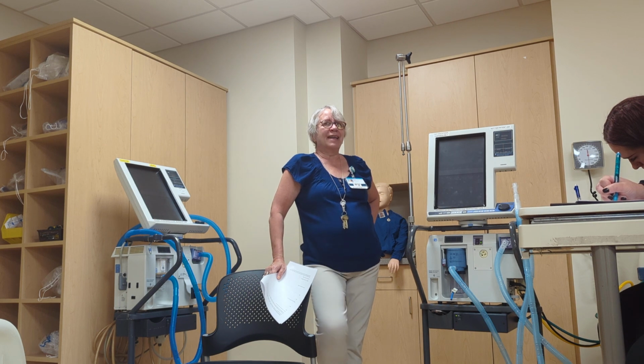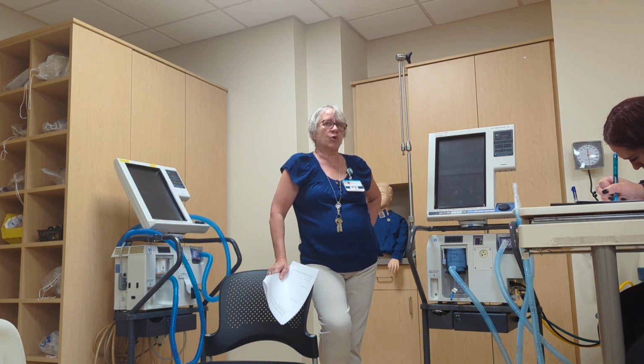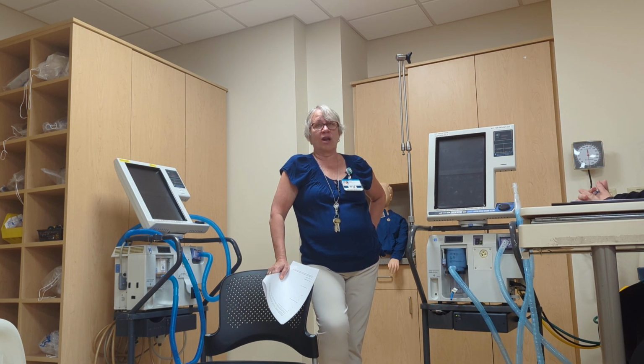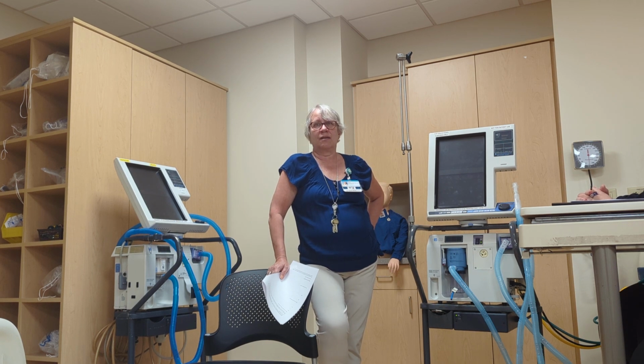We don't run ESTs as respiratory therapists. We take them down to BMET. So that one ventilator that Nick left from the summer and didn't tell anybody about, I have to go take it down to BMET so they can run an EST so we can use it, okay? That one that's in there, and I killed him for it.